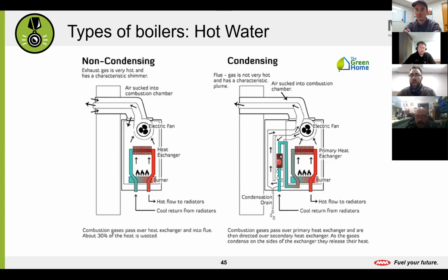What happens is we absorb so much heat out of that gas that the gas temperature drops below our ambient condensing temperature, and so we start to condense, we start to get water. So you'll see on some bigger applications, it may be stainless pipe that's coming out. A lot of smaller ones, you'll see actually PVC pipe as an exhaust. And when you see the exhaust gas coming out of those, it's usually kind of a haze or a fog versus our non-condensing, which is a clear shimmer, right? Condensing is definitely the way to go as far as efficiency. However, that comes with something else that we have to address, and that being the water.